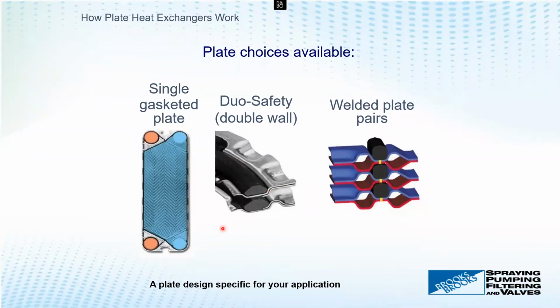So there's no way that it's going to get through this plate and then this plate, because it's not gasketed. So it will just leak, and it's intended to do that. So for instance, if you have domestic hot water, you can't get glycol from the boiler into your hot water for the condos or for the public to consume. So it's very common that they're going to use a duo safety, and there is absolutely no way that the fluids can intermix. They will intentionally leak to the bottom, and that's all by design. So once you see anything coming out, you know that you have to do maintenance.